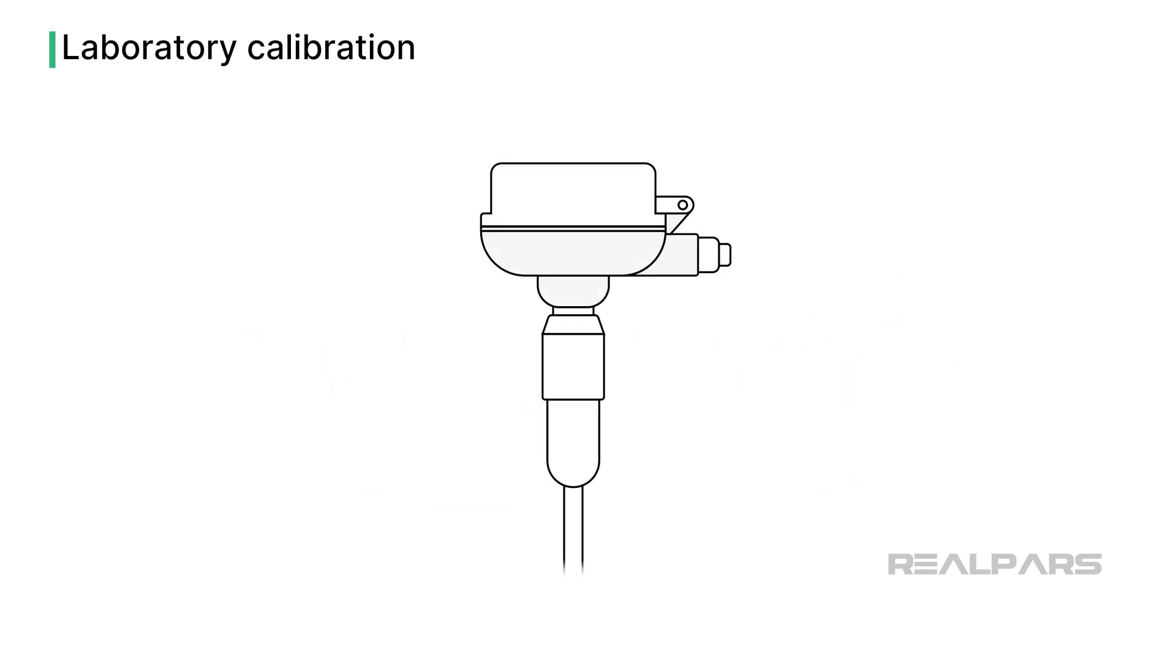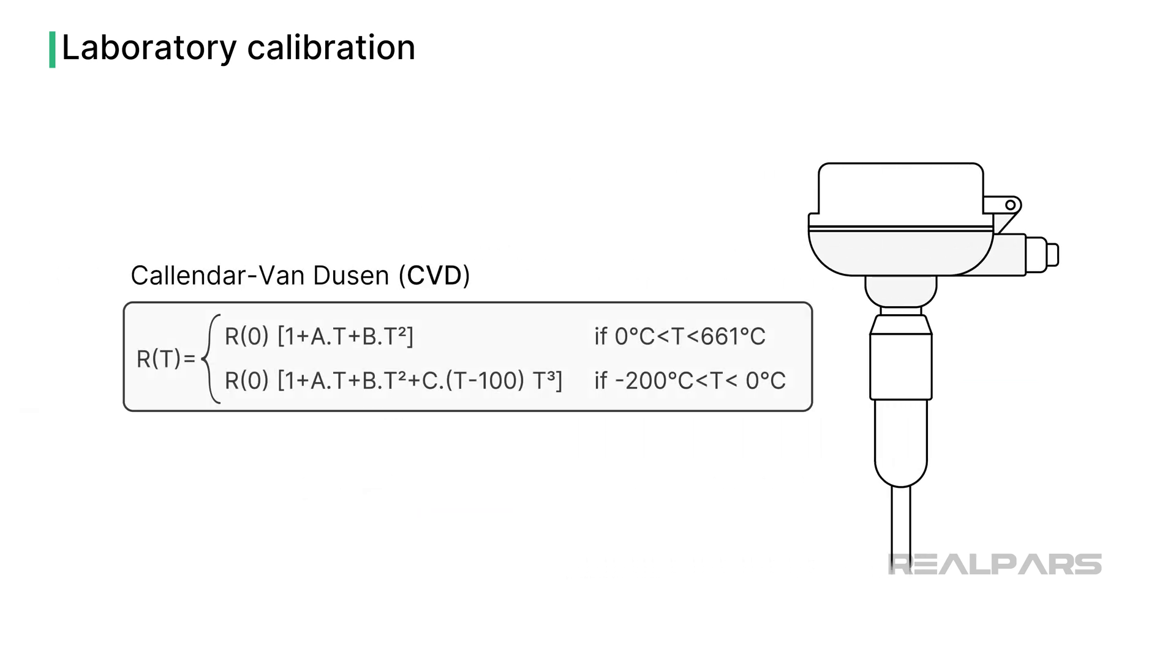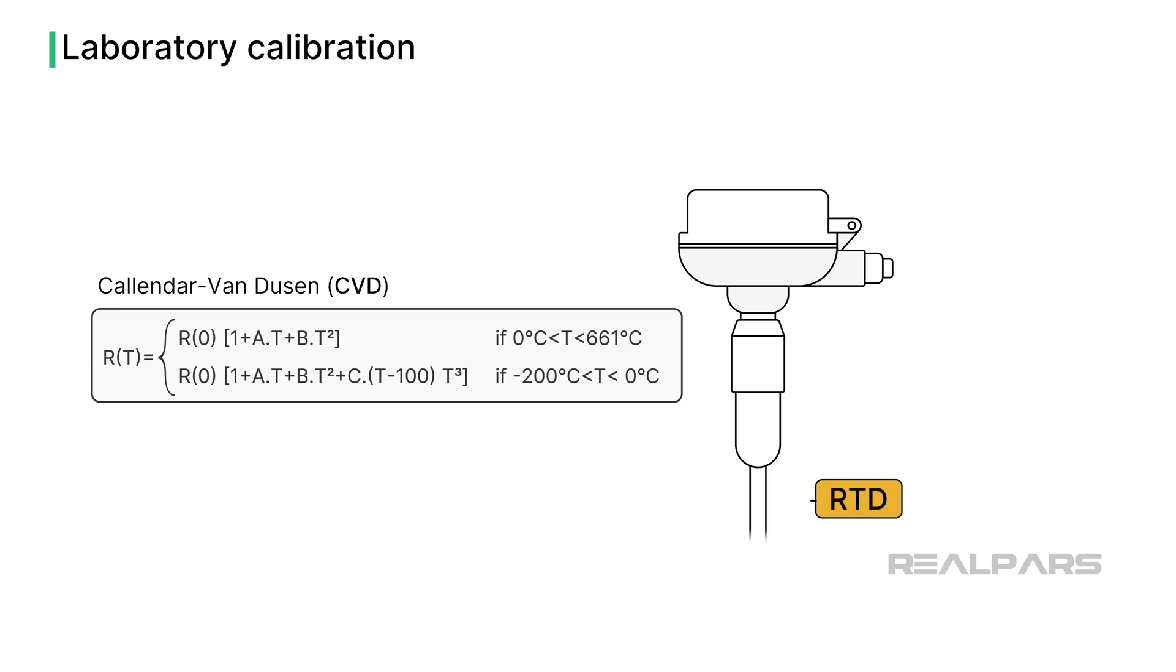Each RTD has unique Callendar-Van Dusen or CVD coefficients, which define its exact behavior. So why not match the transmitter with the RTD during the calibration process using the CVD coefficients?